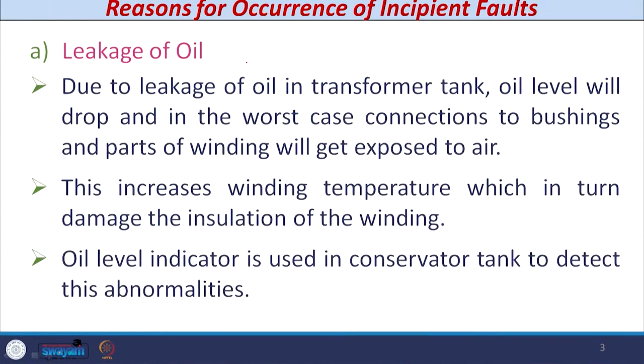The first reason for incipient faults is leakage of oil. Due to oil leakage in the transformer, the oil level may drop and in the worst condition, the bushings and other parts of the winding may be exposed to air. This increases the winding temperature, which in turn damages the insulation of the winding. To detect oil leakage, an oil level indicator is used in the conservator tank of the transformer, and this abnormality can be easily detected.